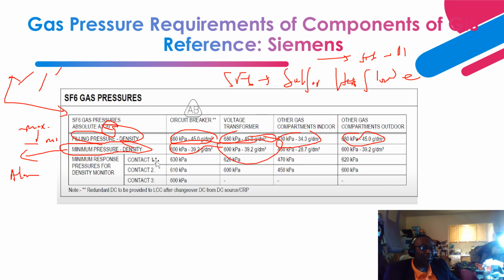Your alarm system at your SCADA works off these values. Once your pressure starts dropping and gets close to your minimum, it will start giving you an alarm for you to investigate. One of the things you want to do is investigate and validate whether it is truly an alarm condition, an SF6 gas leakage. Once it is true, after you validate and do all your leakage testing utilizing portable testing devices, you then have to fill it with SF6 up to the maximum level. So as you approach the minimum level pressure, if you have an SF6 leak, that is when you receive an alarm, and when you receive the alarm, you have to investigate and validate it.